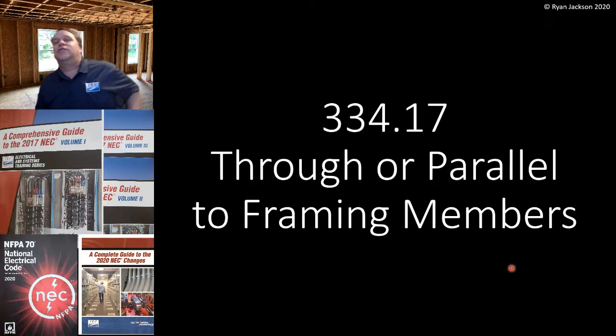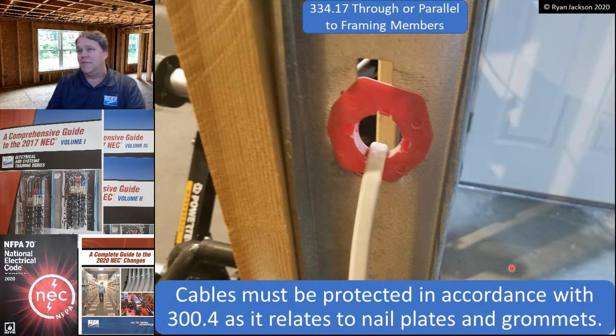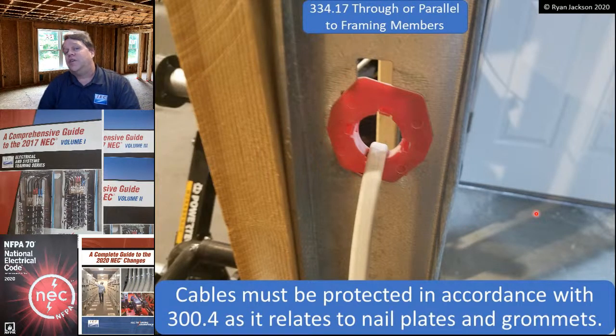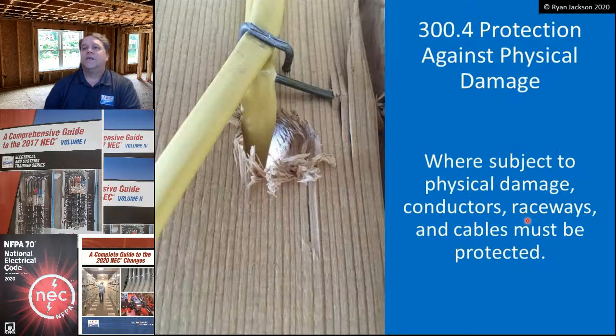Let's keep rolling. 334.17, through or parallel to framing members. All right. Cables must be protected in accordance with 300.4 as it relates to nail plates and grommets. So here is a grommet, a listed grommet at that. Why are we doing this? Well, to satisfy 300.4. 300.4 says where subject to physical damage, conductors, raceways, and cables must be protected. Beautiful example of why we're doing this.